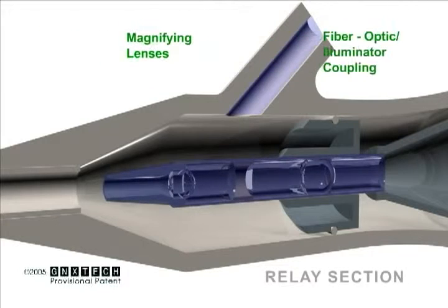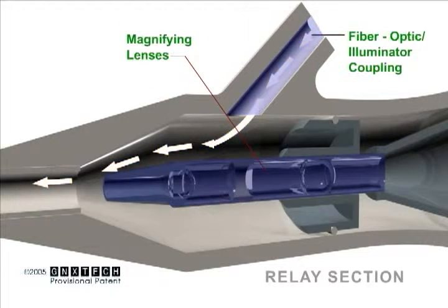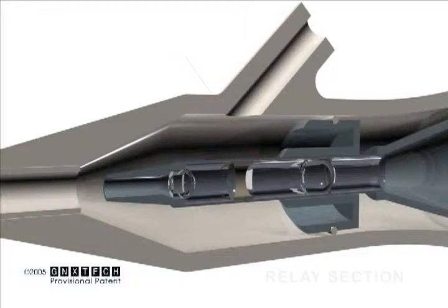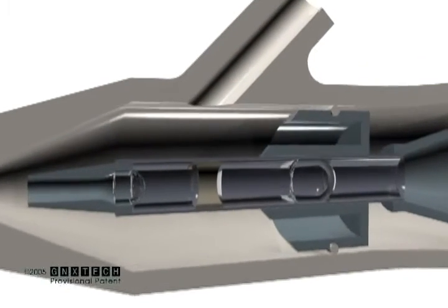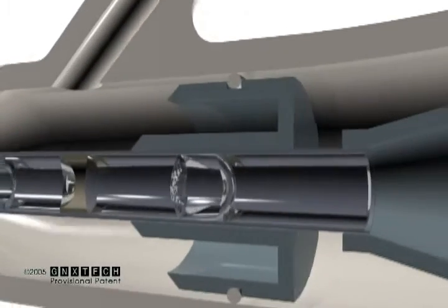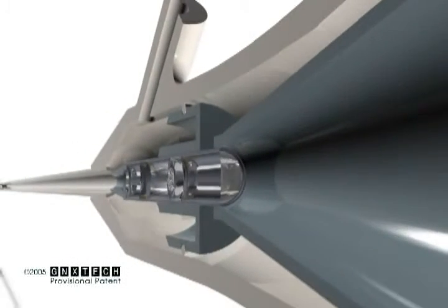First stage magnification of the image trapped in the conduit is then accomplished by the relay magnifier. This section of the endoscope uses precision plastic lenses to enlarge the image without degradation and passes the magnified image to the eyepiece or camera coupling lens that's located at the scope's proximal end.